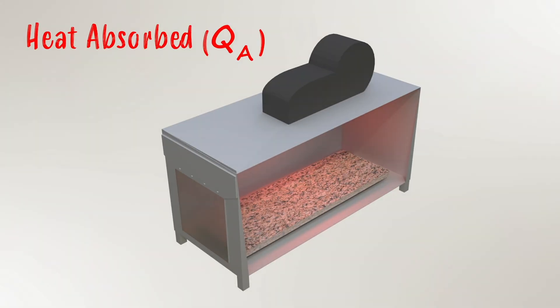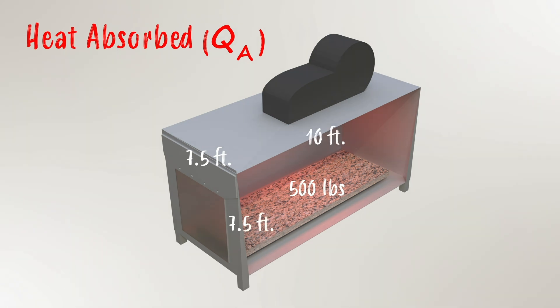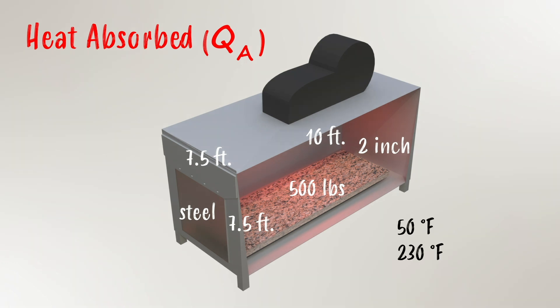Step one: gather information. Let's say you have an oven that is used to heat 500 pounds worth of granite blocks in a batch process. The oven is seven and a half feet wide, seven and a half feet high, ten feet long, and has steel walls with two-inch thick fiberglass insulation. In this scenario, we need to determine the amount of heat in kilowatts absorbed by the granite as they're being heated from 50 degrees to 230 degrees in two hours.